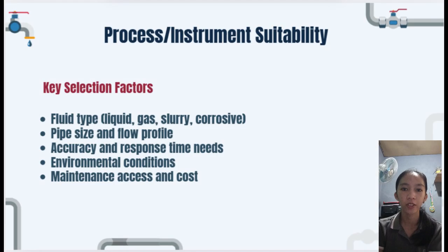This brings us to the most critical part. How do you choose? You need to ask, what is the fluid? Is it liquid, gas, slurry? Is it clean or dirty? Is it corrosive? What are the pipe and flow conditions? What's the diameter? Is the flow steady? What are my performance requirements? How accurate do I need to be? Do I need real-time control? What is the installation environment like? Is it hot? Is it accessible? Answering these questions is the first and most important step.